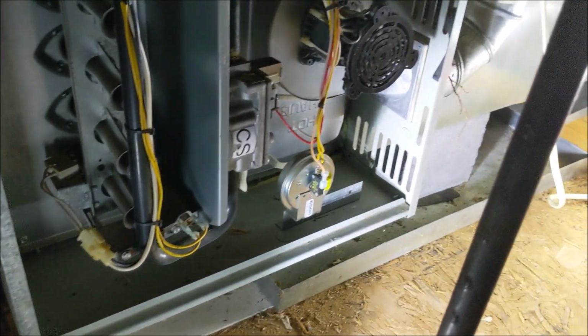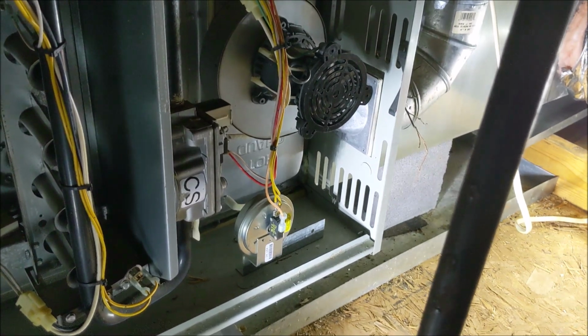All the monoport burners look good. The air flow and the system looks good. There's no rust or anything. Gas valves in good place. Shut-off valves are good. Wiring looks good. A little bit of dust in here. Probably could use some vacuuming on some of the squirrel cage motor, the actual motor. It's not the motor, but the squirrel cage itself at both units, just as general cleaning.